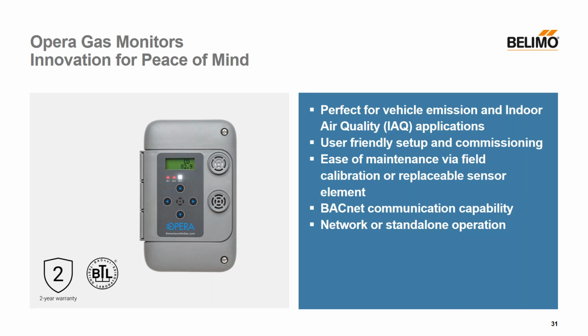Features a universal robust enclosure with electronic display with LED visual and audible alarm indication. They're offered with single or dual integral electrochemical sensor. The field replaceable sensor promotes simple and easy on-site calibration. Combined CAN bus or BACnet MSTP networks allow for seamless integration into an existing network or standalone operation. And analog output and relays allow on-demand ventilation without the need for an additional controller.